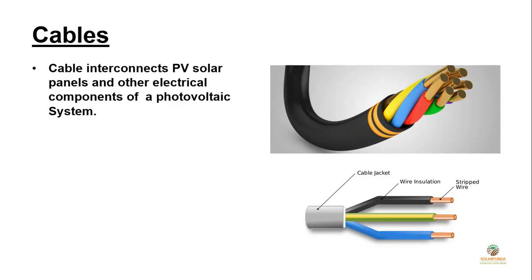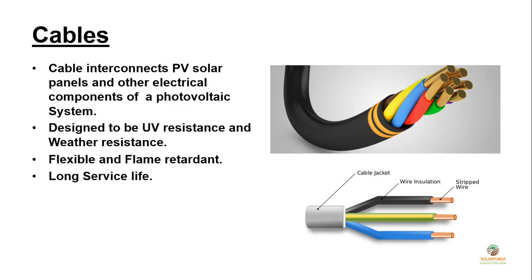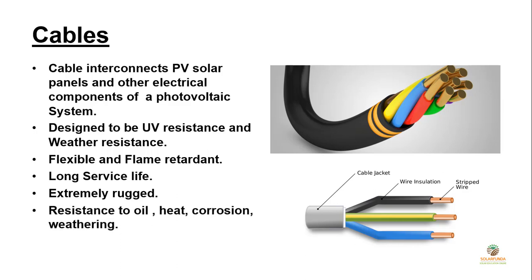You can find cables and wires everywhere because electricity has reached every corner of your house. Talking about the properties of cables used in solar PV systems: cables should be designed to be UV — that is ultraviolet radiation — and weather resistant. Cables should be flexible and flame retardant. They should have a long service life, must be extremely rugged, and should be resistant to oil, heat, corrosion, and weathering. These properties are required because generally solar cables are laid outside.